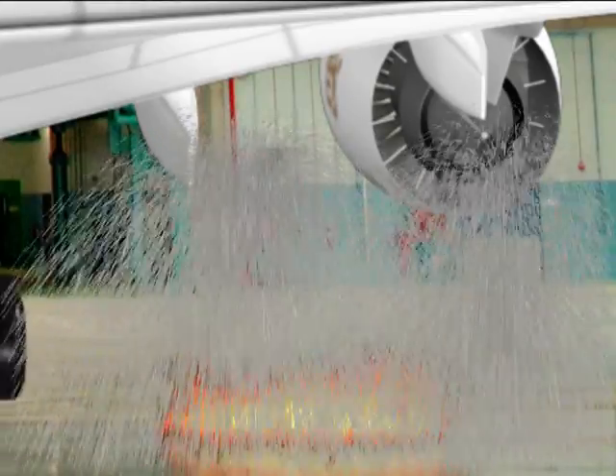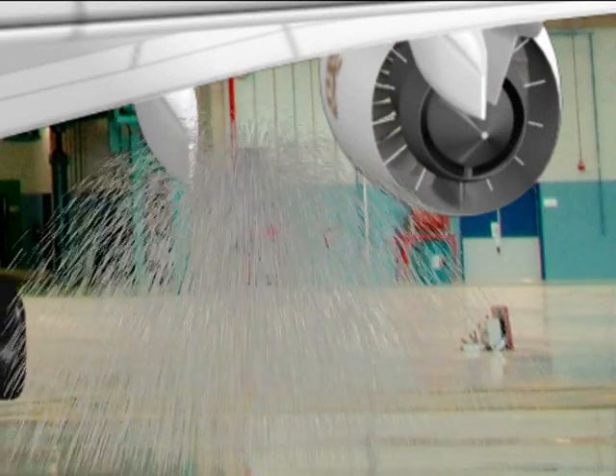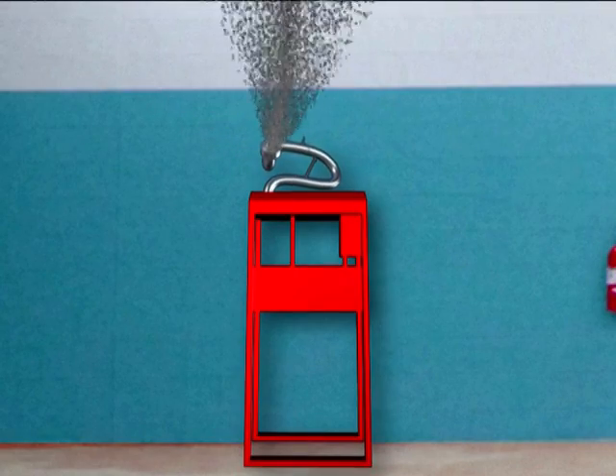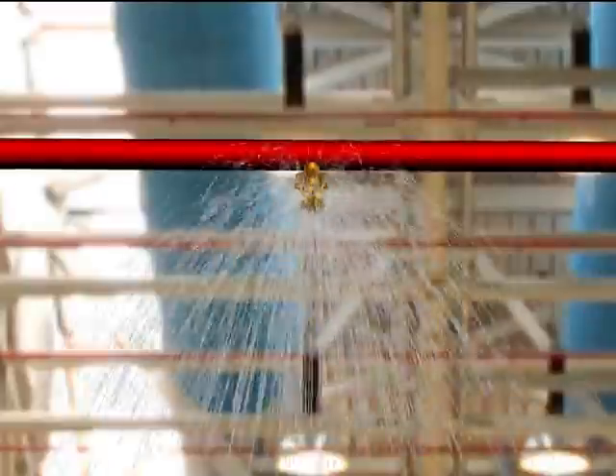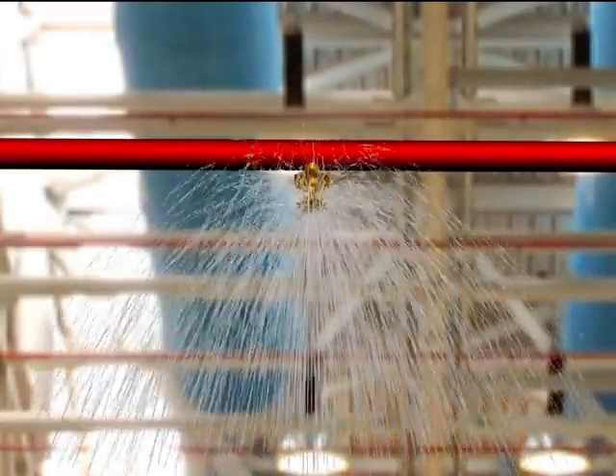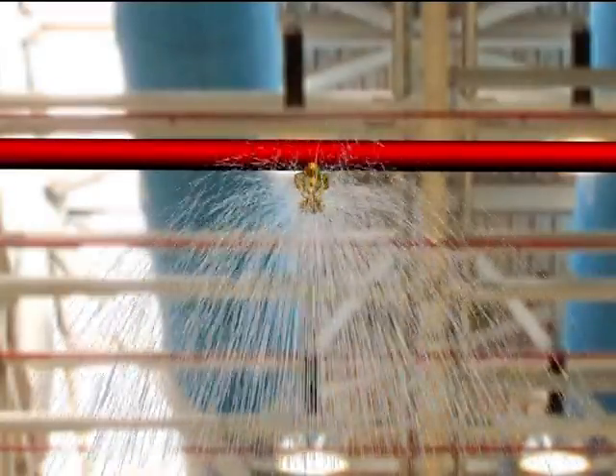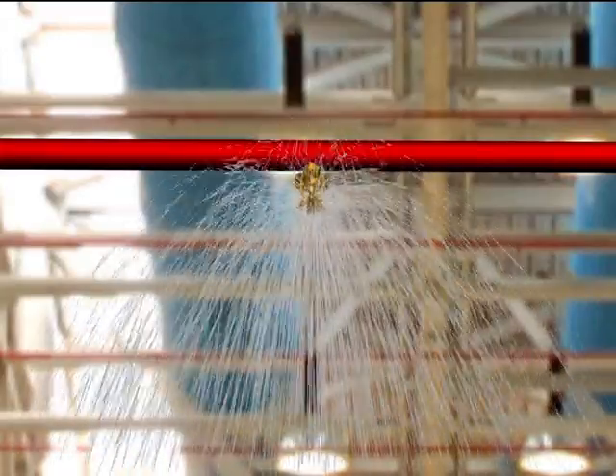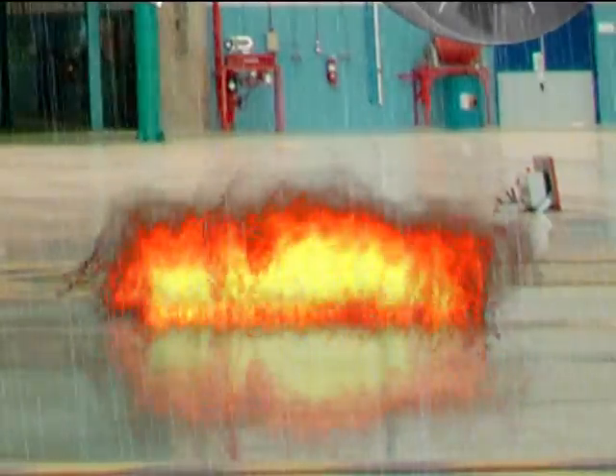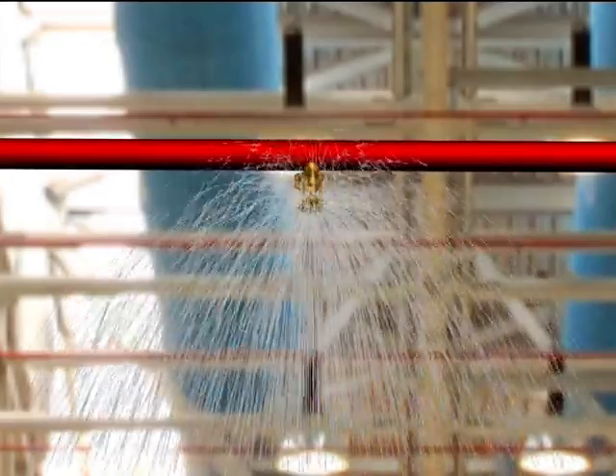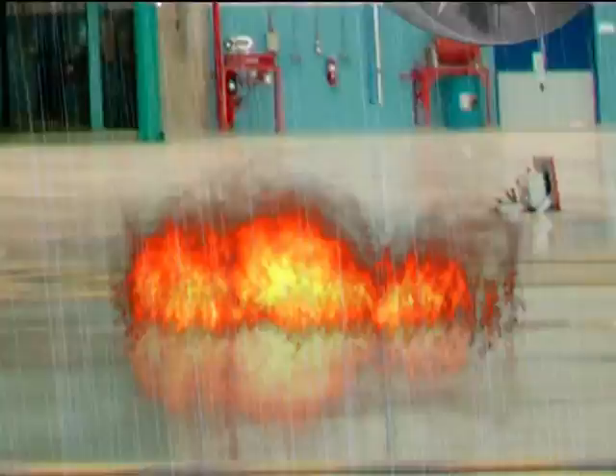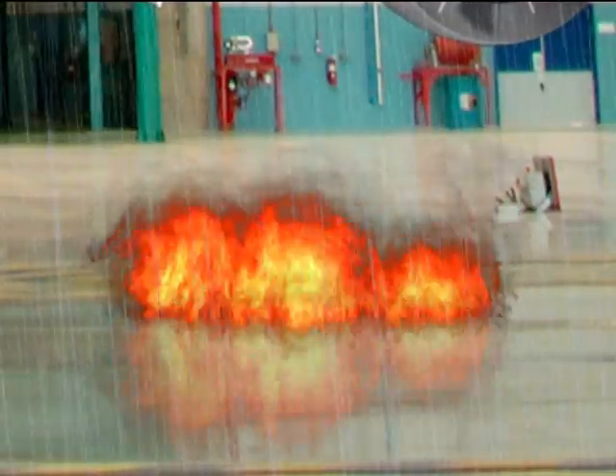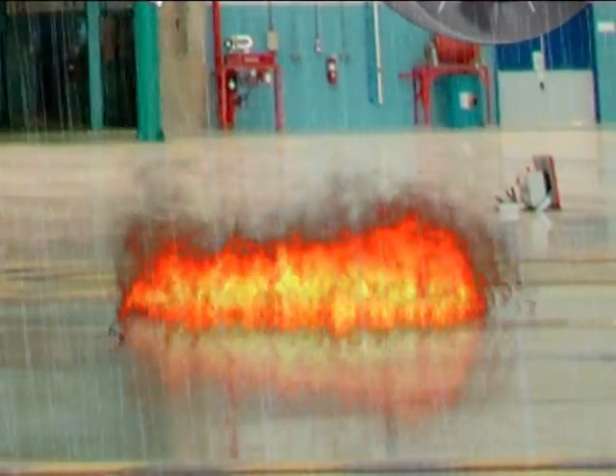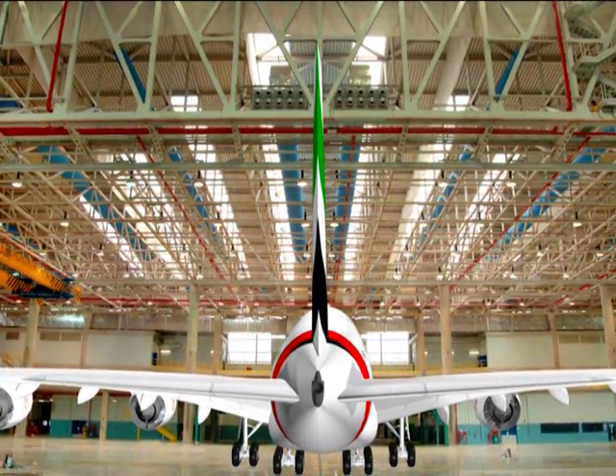These water cannons can also be controlled manually if necessary. Within 10 seconds of fire detection, the overhead sprinklers start sprinkling a mixture of foam and water from the ceiling in a 30-meter radius of the coordinates of the fire. The deluge system takes away 2 out of the 3 components required for fire. It reduces temperature and separates oxygen from the fire. So even if the third element, which is fuel, is present, it is rendered harmless by the deluge system.